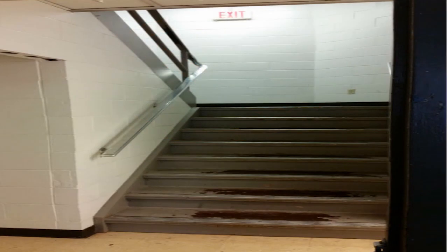It's not required in all stairwells, but we're going to talk about the scenario when it is required. According to the NEC, you could literally have a hundred-foot-long hallway and only have one switch in that hallway. Even a large room — not required. The only required place is in stairwells. Let's look at what the code says, here in this stairwell.